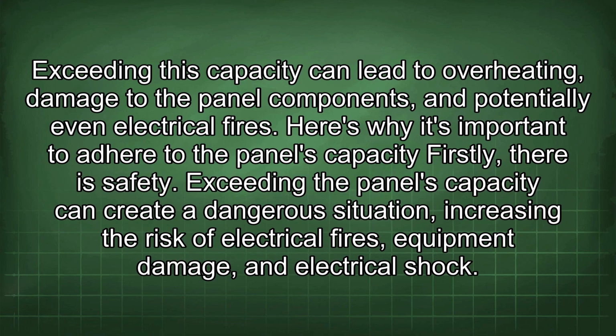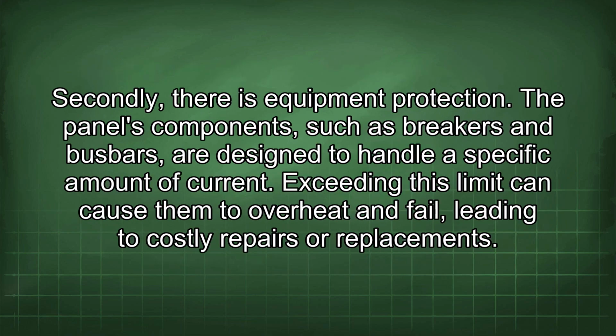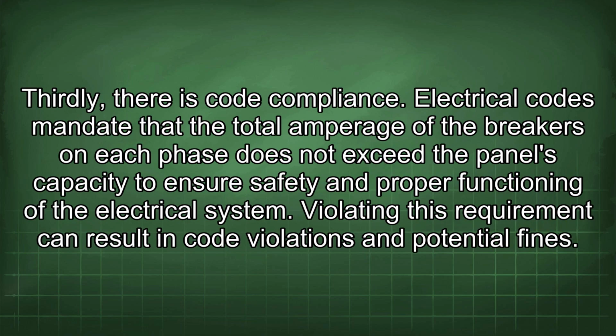Firstly, there is safety. Exceeding the panel's capacity can create a dangerous situation, increasing the risk of electrical fires, equipment damage, and electrical shock. Secondly, there is equipment protection. The panel's components, such as breakers and busbars, are designed to handle a specific amount of current. Exceeding this limit can cause them to overheat and fail, leading to costly repairs or replacements. Thirdly, there is code compliance.